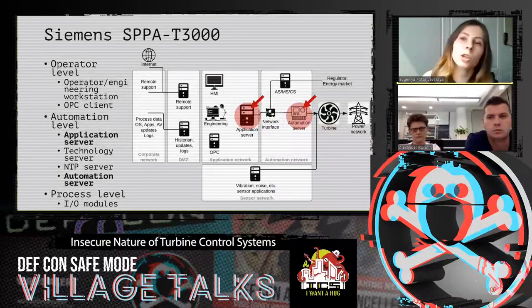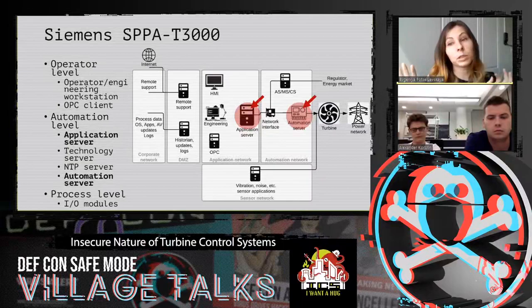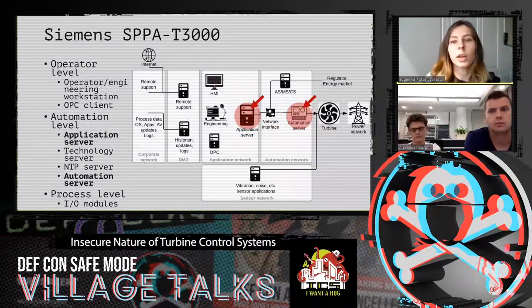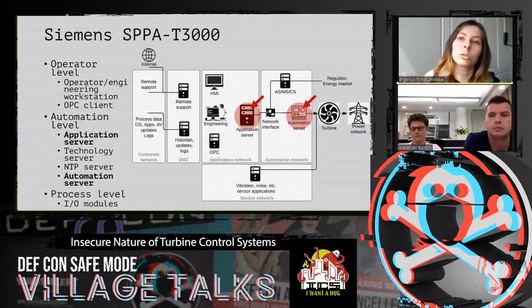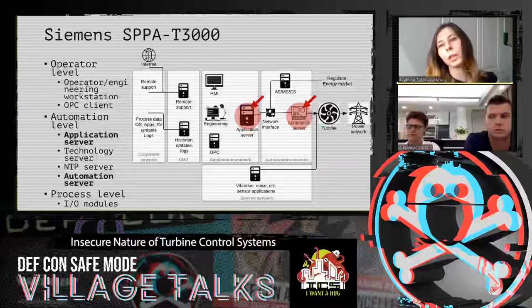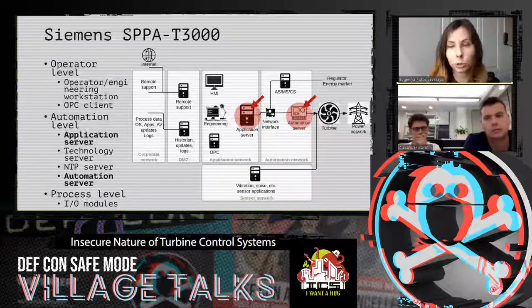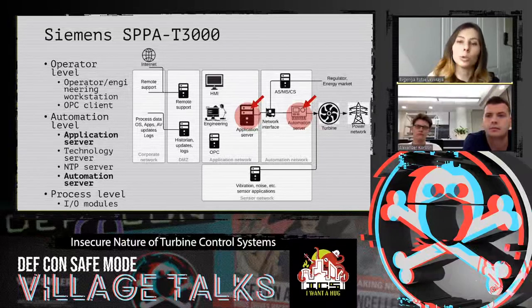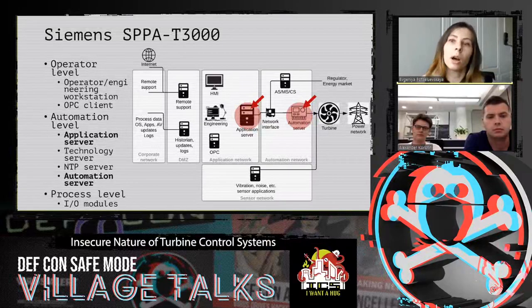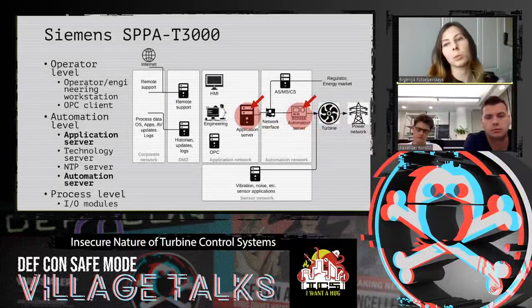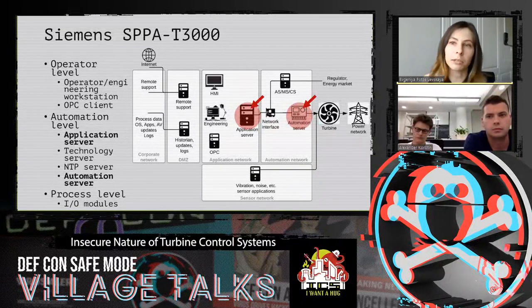In different manuals and documentation from Siemens, you will see how the system should be built in a perfect world — for example, they will say that the application network should never be connected to any external networks. However, in reality, in real power plants you will need a lot of interconnections to other systems: a sensor network to monitor vibrations inside the turbine, a DMZ for remote support from the vendor, updates for operating systems, pushing OPC traffic to a corporate network or to a regulator because this area is very strictly regulated. So in practice you will need a lot of interconnections.